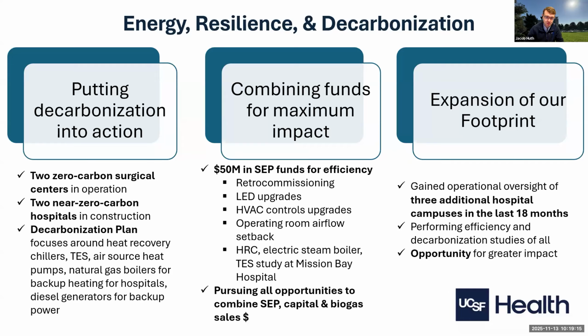Combining funds has also been a major point for UCSF Health. We got $50 million in SEP funding for energy efficiency, and we're currently running projects in retro-commissioning, LED upgrades, HVAC control upgrades, and operating room airflow setback has been a big focus. There's significant savings from turning down airflow in operating rooms when they're not in occupied mode, as well as putting in heat recovery chillers where possible at other plants. We're pursuing all of this by combining SEP funding, capital funding, and biogas sales.